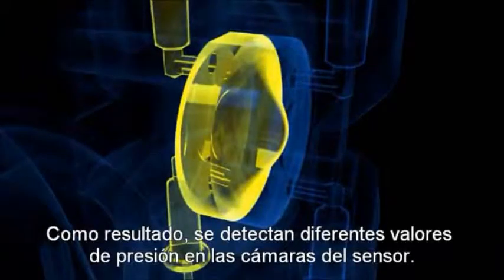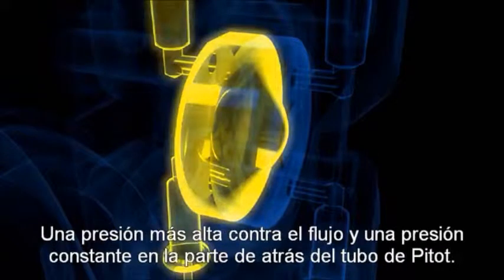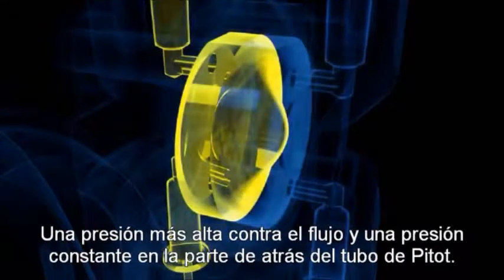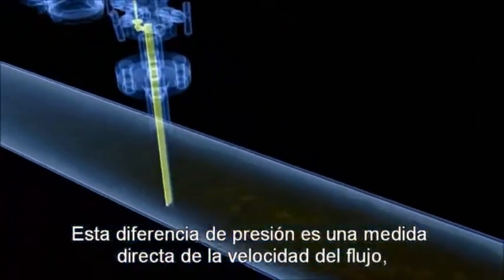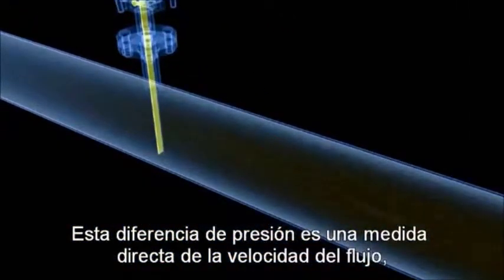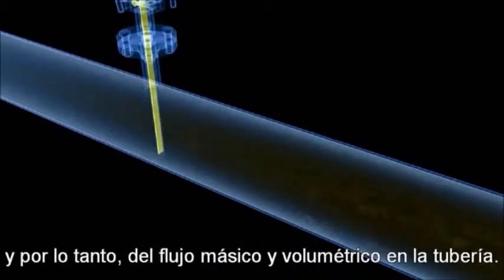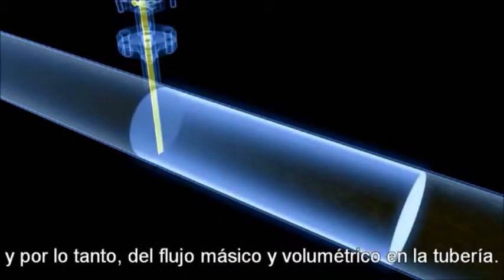As a result, different values are detected in the pressure chambers of the sensor. Higher pressure against the flow and constant pressure on the rear of the Pitot tube. This pressure difference is a direct measure for the flow velocity and thus the mass and volume flow in the pipe.